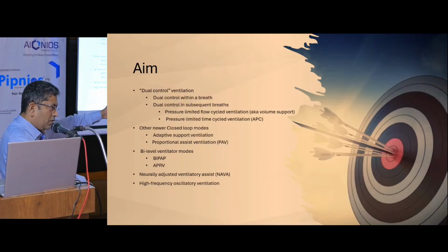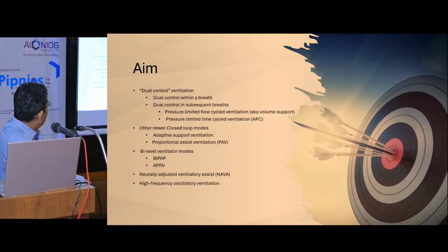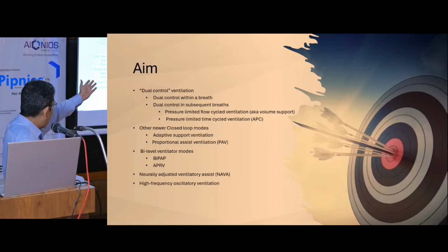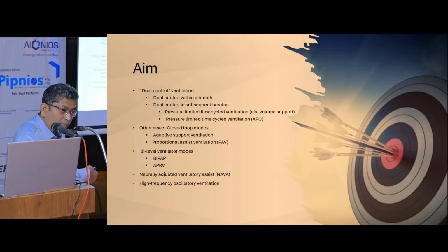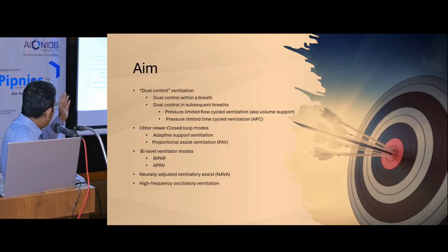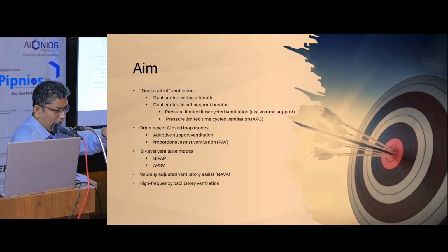Then there is dual control in subsequent breaths, or changes across breaths. Those are pressure limited flow cycle ventilation or volume support, or pressure limited time cycle ventilation. We'll come to that. Generally that is PRVC, pressure regulated volume control, or APC, adaptive pressure control. Then there are other newer closed loop ventilation modes: adaptive support ventilation, which you would have heard of, and proportional assist ventilation, called PAV. These use algorithms to change your support from the ventilator.